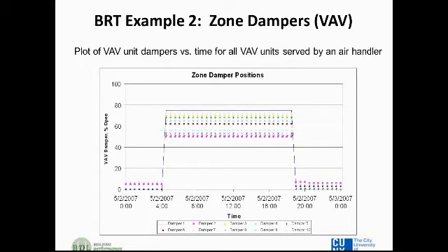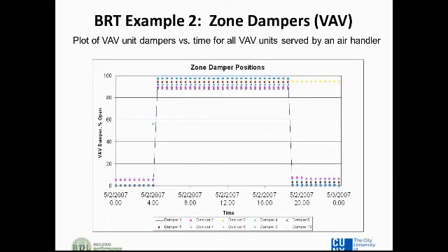Let's say you've got dampers in your VAVs, and you want to track the damper positions. In this case, you can see that we're plotting 10 dampers. They all seem to be open during occupied hours between 50 and 75%. That's considered good operation. And you can also see that this is going on during what is presumably occupied hours. Now, it's probably possible in this case that you could narrow down the hours of operation. It looks like the dampers are opening at 4 in the morning. I don't know if the supply fans are on at this point, but there doesn't seem to be any need for the dampers to be open at that early hour unless you've got an early shift going on in this building. So we've got the dampers essentially closed for the most part, or closed way down during the unoccupied hours, and then open at an appropriate level, 50 to 75%, during occupied hours. That's an example of good operation.